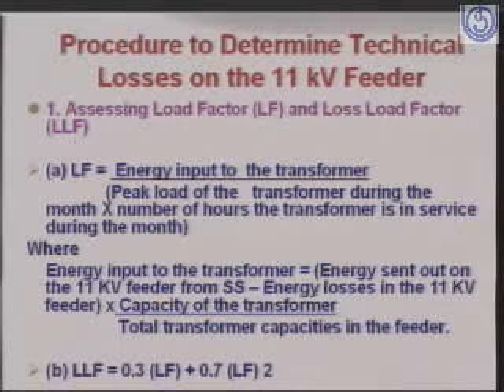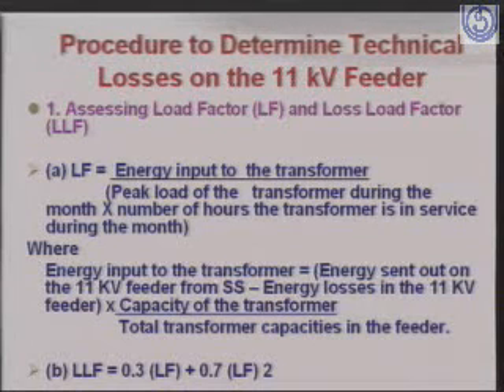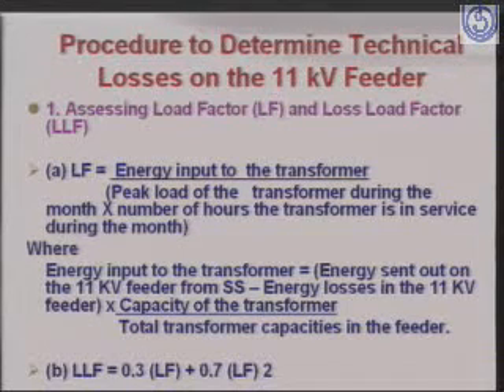Procedure for determining the technical losses on the 11 kV feeder. It's a step-by-step approach which is very well covered in your course books. I am just giving the summarized version of the assessment procedure. First we find out the load factor. Basically it is the energy input to the transformer, that is on the primary side. If you have a meter, then we know the energy being supplied to the transformer, divided by the peak load of the transformer during the month.